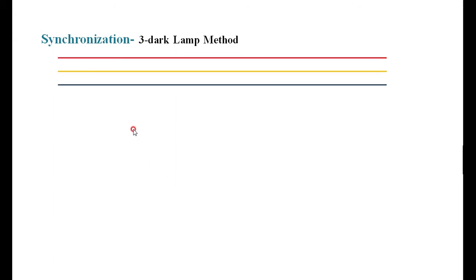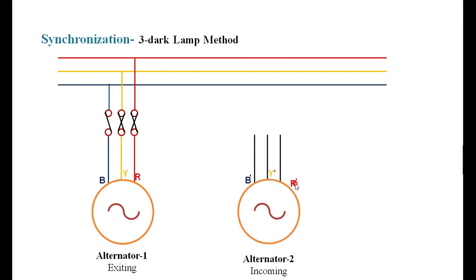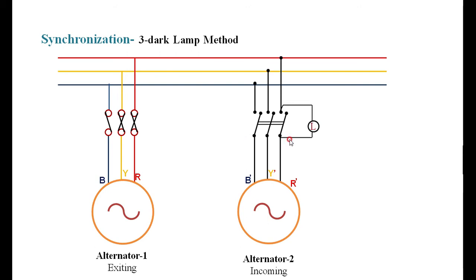One synchronization method I am discussing here is the three dark lamp method. I have a bus bar with R, Y, B phases, and alternator one is the existing alternator already connected to the bus bar. To connect alternator two in parallel, you should not connect directly to the bus bar. Instead, through a switch, I am connecting three lamps across each phase between the alternator and the bus bar — the first lamp, second lamp, and third lamp across all three phases.